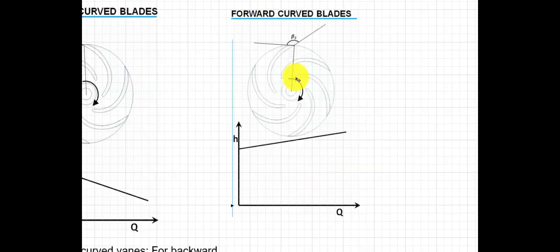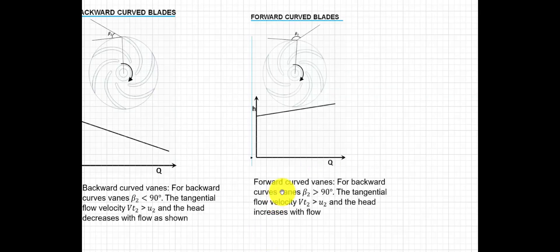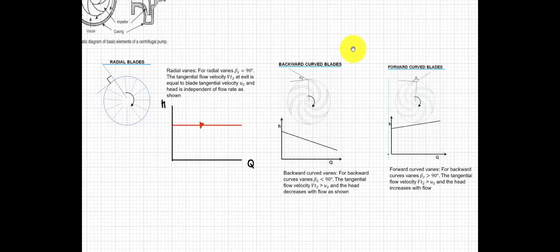Next, we have the forward curve blade. You'll notice the angle is already greater than 90 degrees. If you plot the head versus the volume flow rate, we have an increasing head and also an increasing volume flow rate — as you increase the volume flow rate, the head also increases. For forward curve vanes, the angle is greater than 90 degrees, vt2 is greater than u2, and the head increases with the flow. The question is: which blade type is most suitable for industrial use?